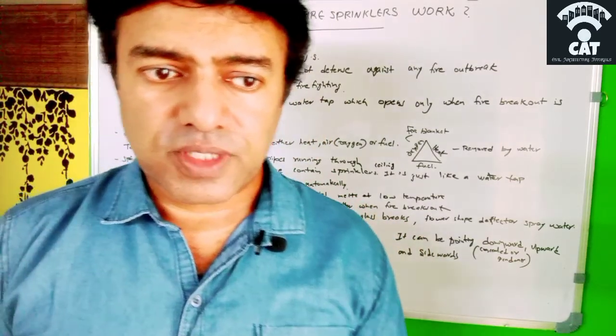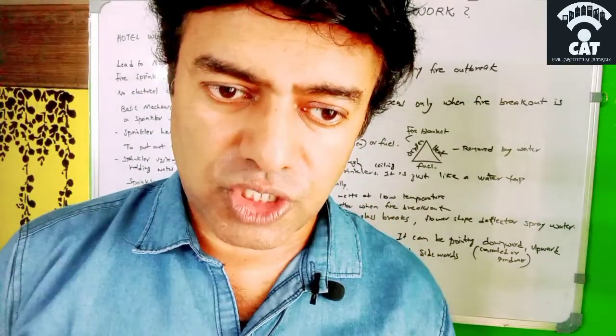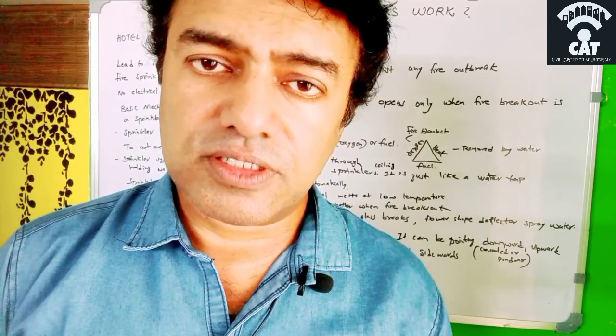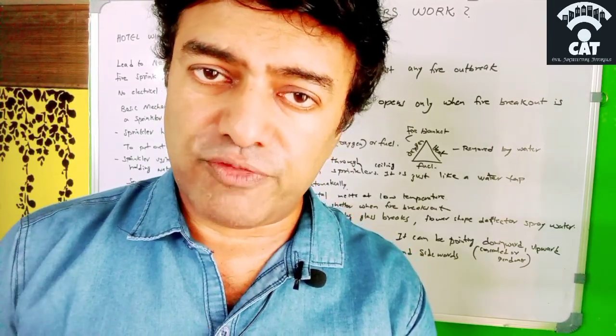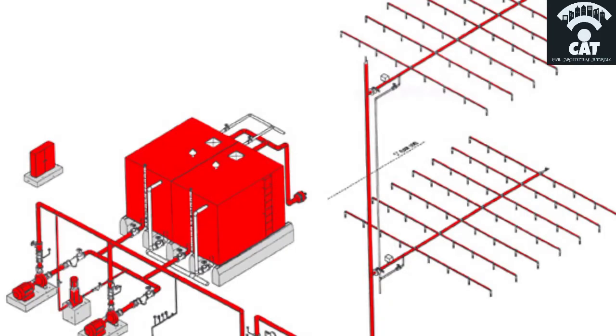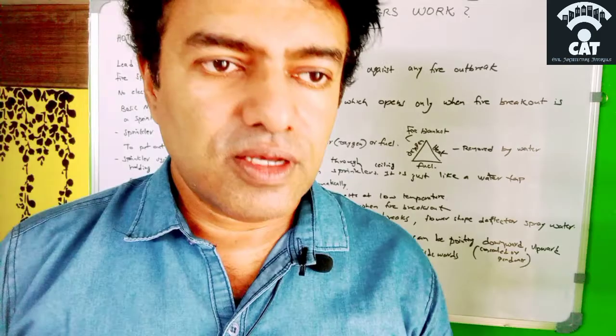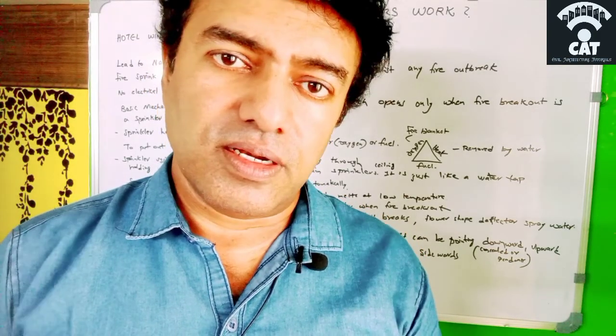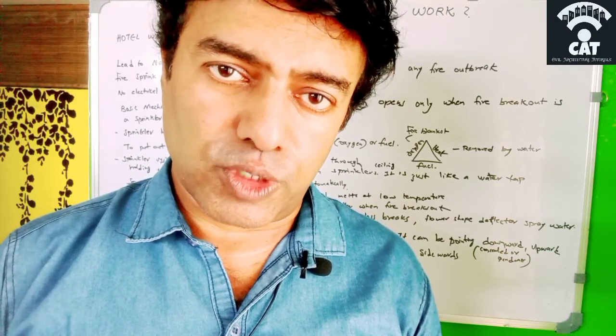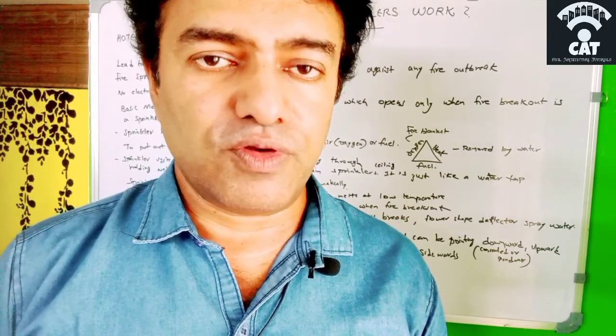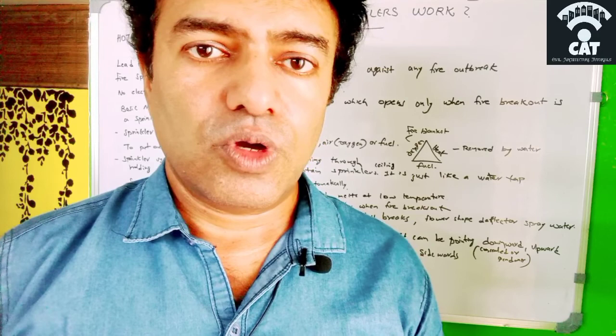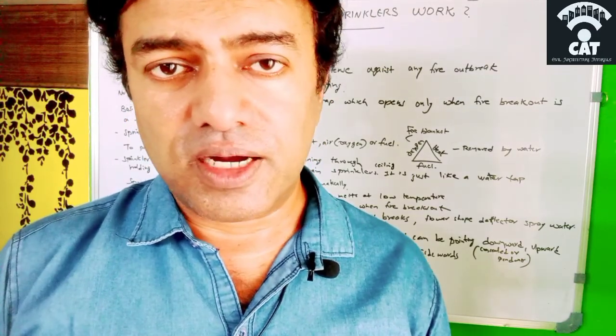When we introduce a sprinkler system or any fire safety system, it is the first line of defense against any fire outbreak in a building. Considering that, we cannot use any electrical circuits or electrical devices in the fire defense system, because when a fire breaks out, it will destroy all electrical circuits or devices, and they will not function. Even in case of lightning, the electricity will not function.